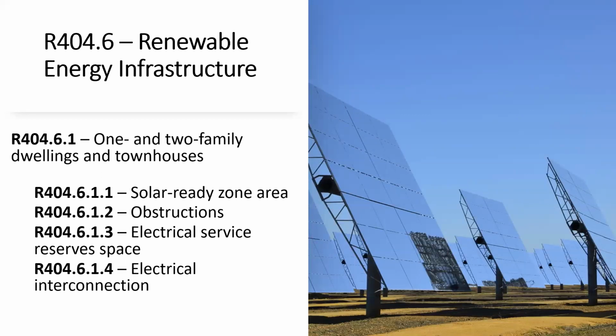And then obstructions, it says solar ready zones shall be free from obstructions, including but not limited to vents, chimneys, and roof mounted equipment. Electrical service reserved space: the main electrical service panel shall have a reserved space for a dual pole circuit breaker and shall be labeled as, quote, "for future solar electric." The reserved space shall be at the opposite load end of the bus bar from the primary energy source.